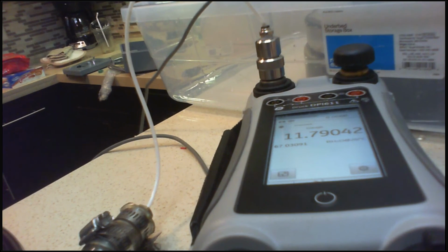And you don't need to see that calibrator anymore because it's not as interesting to look at. So one thing you can do with this is, all right, we found the slope, but you can actually track that over time too. Every time you're up there, every 6 months, you are getting a slope, and that's something that you can record.